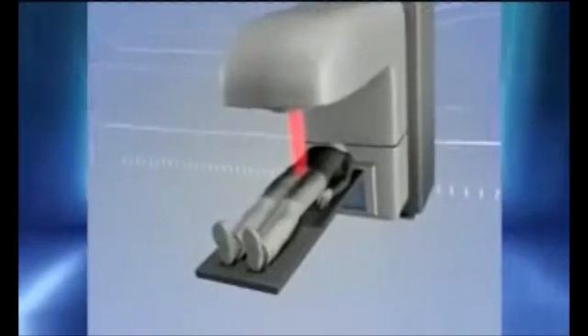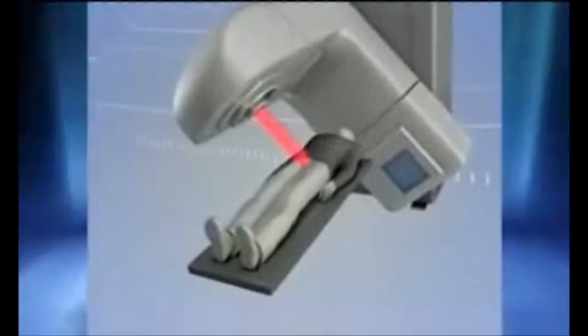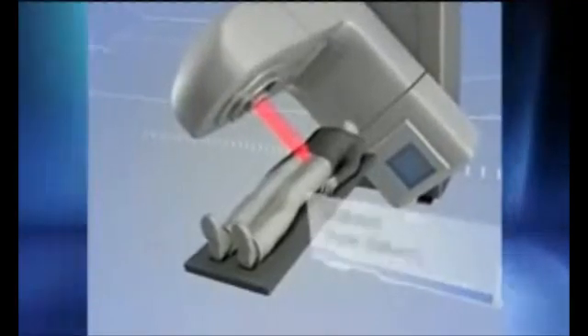Gantry-based systems, which are constrained to clockwise and counterclockwise rotations, typically only deliver 5 to 7 beams or a single arc over an axial plane. While this may be a suitable approach for low-dose radiotherapy, it is often not well-suited for prostate radiosurgery, as extremely high doses are focused to very limited beam entrance and exit points.